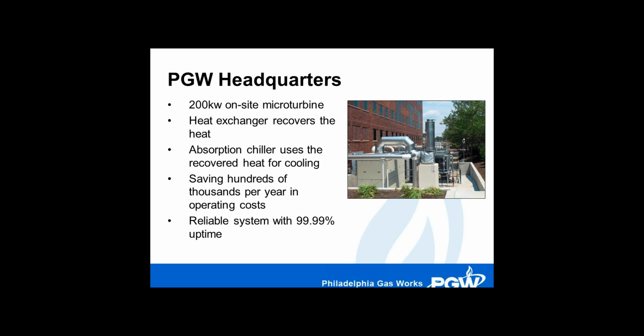The second small box is the heat exchanger, which takes the heat generated from the microturbine, between 400 and 600 degrees Fahrenheit, and uses it for heating during the cold season. During the warm season, we put the heat through an absorber, which is our third part. For someone who doesn't know what an absorber is, it's the magic box where heat enters on one side and cooling comes from the other side.